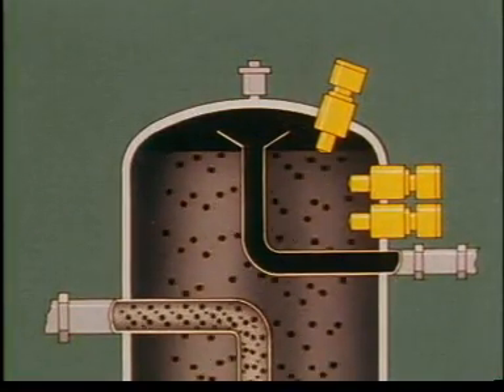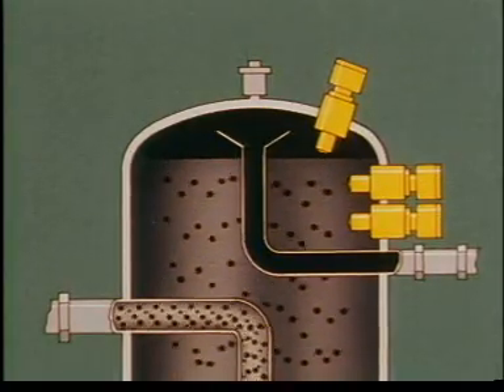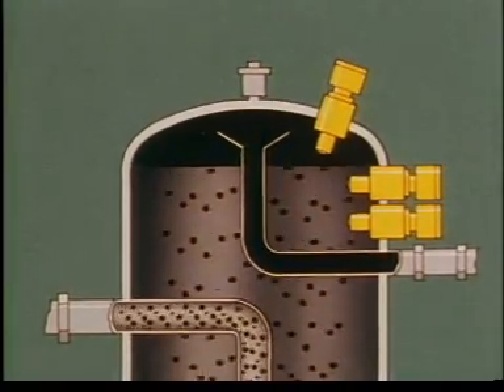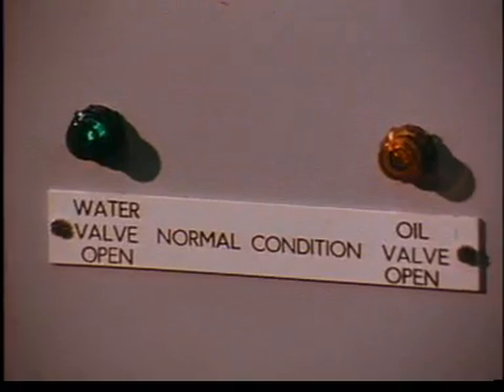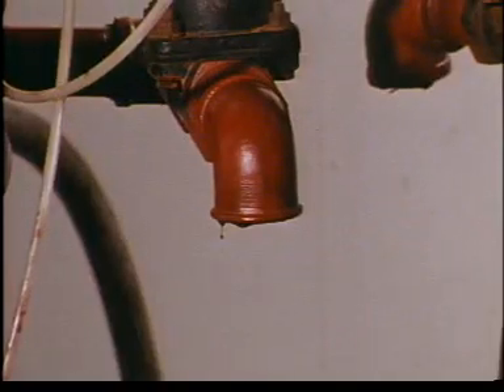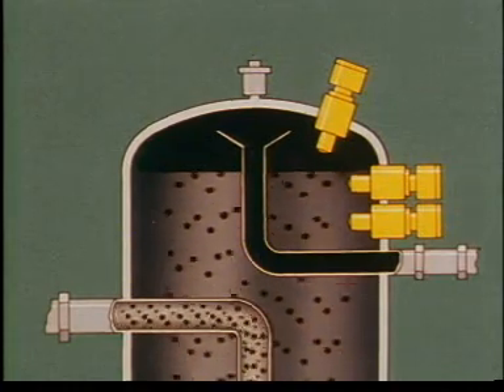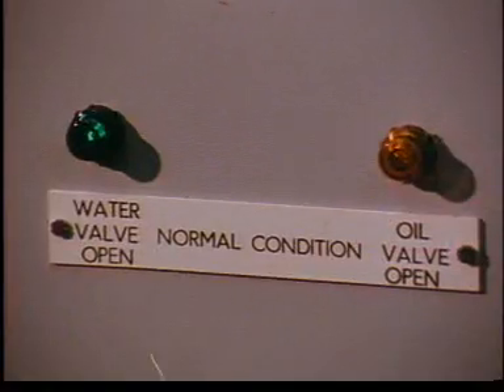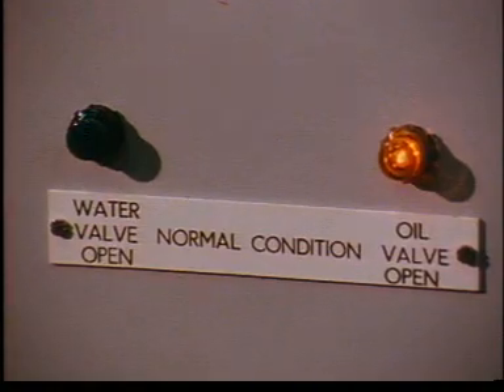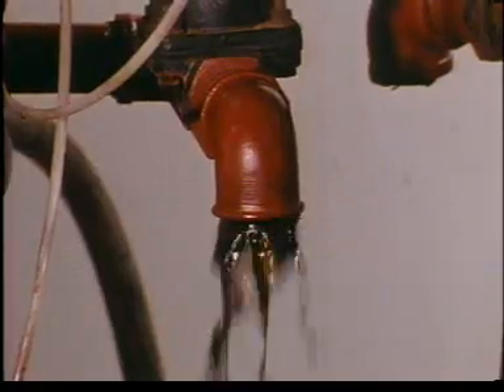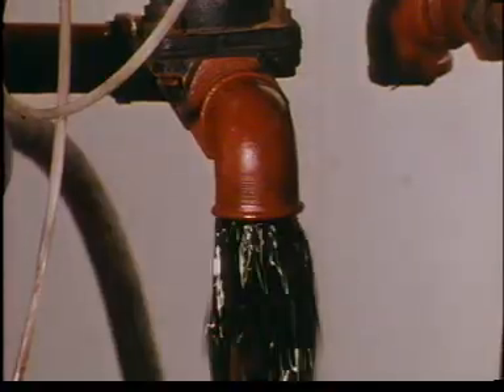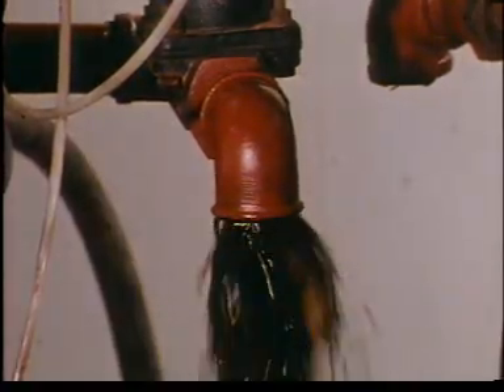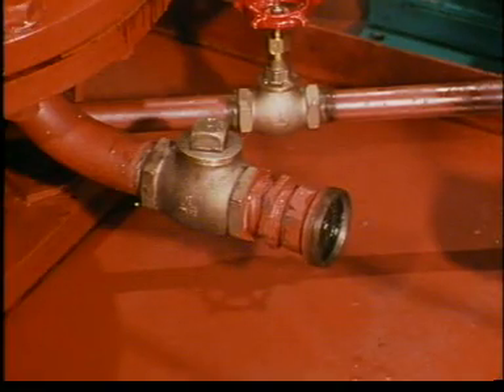Oil globules continue to accumulate at the top of the separator, and the oil-water interface slowly descends. The high-level light on the control panel remains showing water. The oil outlet valve remains closed, and no flow of oil goes to the storage tank. Presently, the oil-water interface again gets down to the middle probe, and the high-level light on the control panel changes from water to oil. Control air to the oil outlet valve is now cut off, and the oil valve opens, allowing oil to flow out. The pressure in the system is relieved, so the spring-loaded water discharge valve closes.